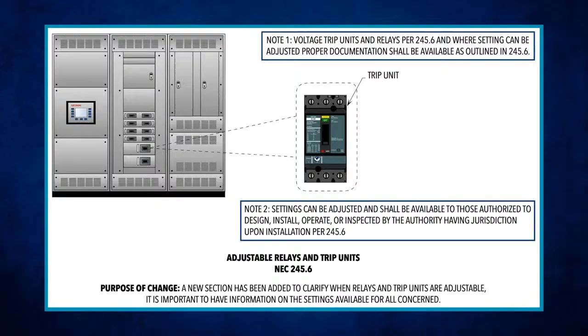True, I think that's kind of important. I've seen that before. We had a case where the engineer gave us instructions to set our TCCs at 10% or something, and we went and set them all exactly, with paperwork showing exactly what to set them at. Then an engineer came by and asked why we set them at that, explaining that the trip curve was way higher, that we were supposed to be set at like 80%. So that documentation is important because it gives anyone a chance to look at it and say, no, you did that totally wrong. We had all the documentation, showed them, and they confirmed it was exactly wrong - whoever told us to do that was wrong. So that's probably a good change.